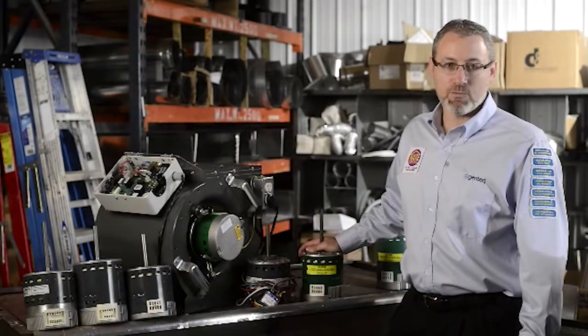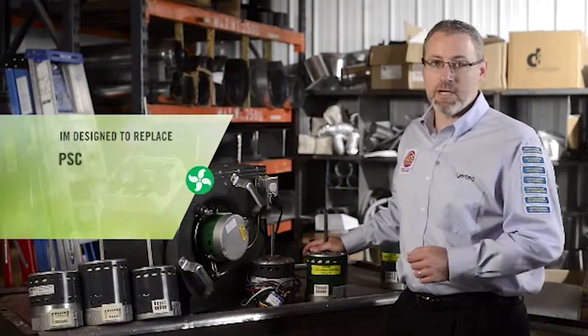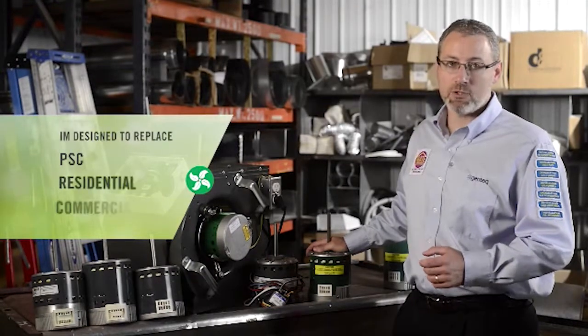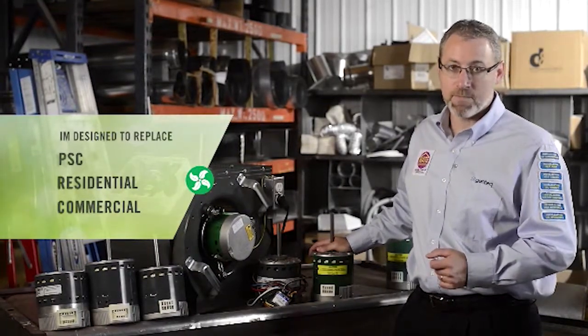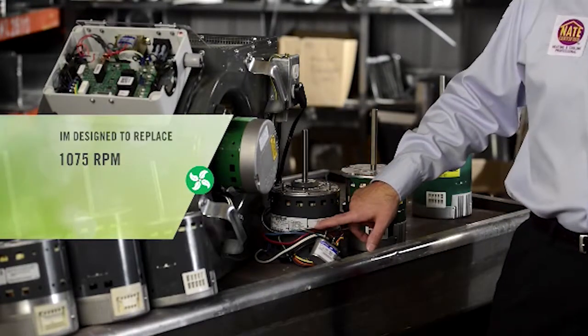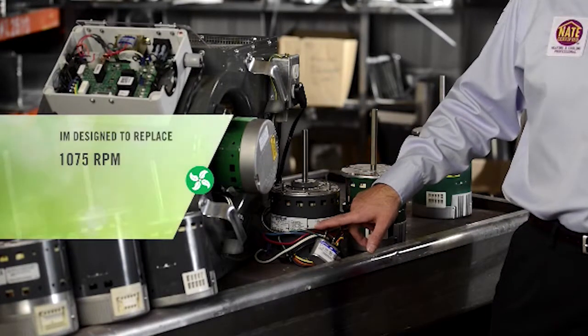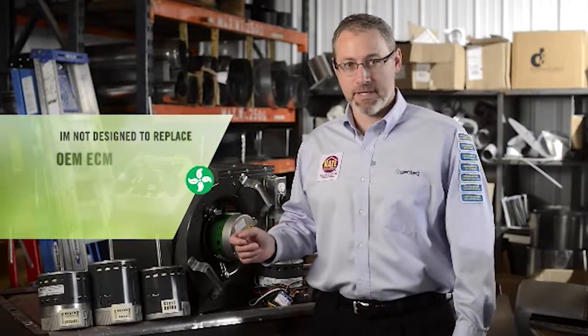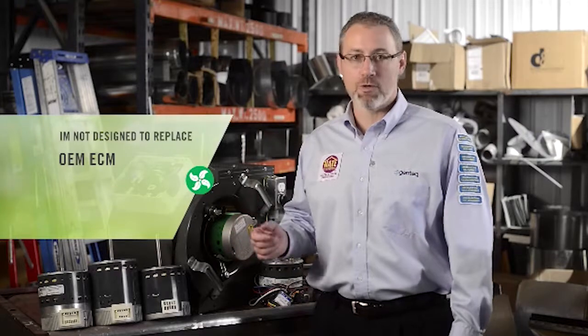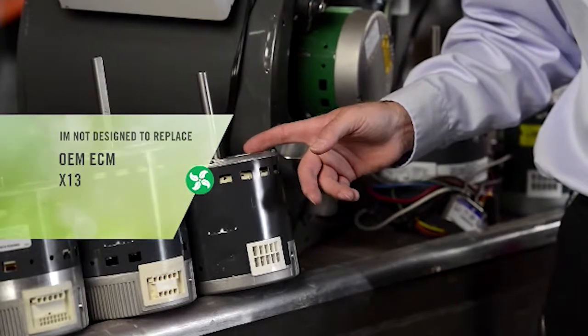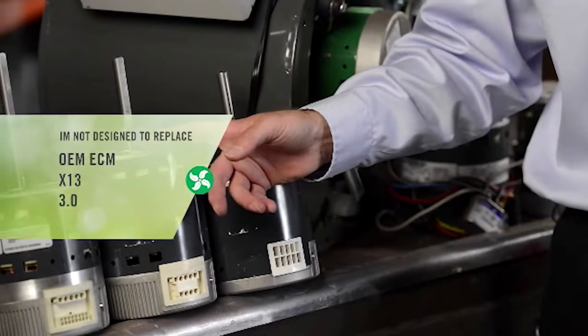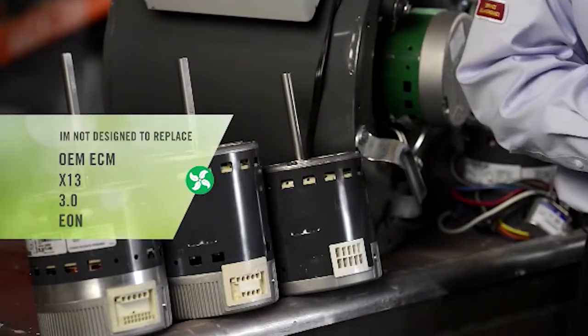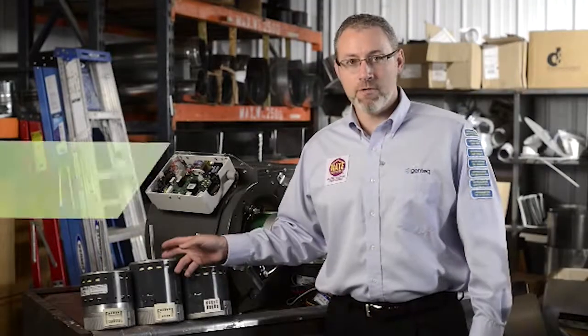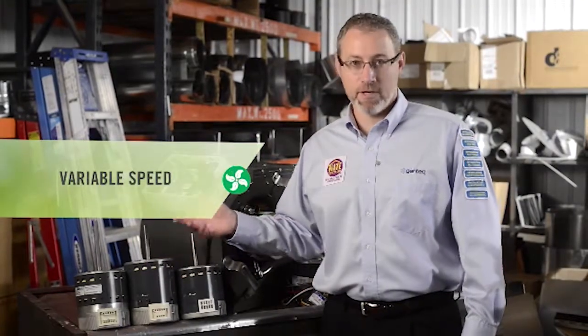Let's talk about applications and ratings. The Evergreen IM is designed to replace PSC motors in residential and light commercial HVAC systems. Specifically PSC motors that say 1075 RPM on their rating plate. The Evergreen IM is not designed to replace OEM ECM indoor blower motors, such as the X13 24-volt multi-tap motor, or the Model 3.0 communicating 4-pin motor, or the Model Eon 16-pin communicating motor. These two communicating motors are often referred to as variable speed.